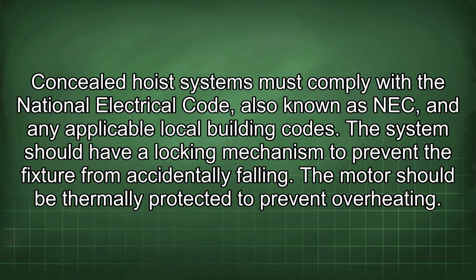Concealed hoist systems must comply with the National Electrical Code, also known as NEC, and any applicable local building codes. The system should have a locking mechanism to prevent the fixture from accidentally falling. The motor should be thermally protected to prevent overheating.